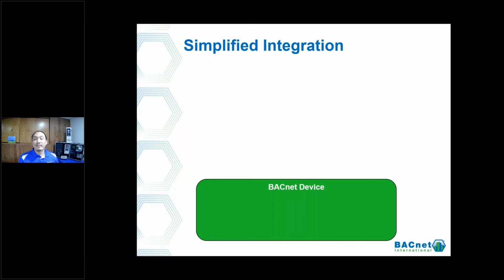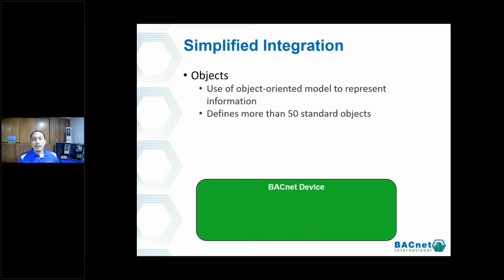Now that I know what my device is going to be, I need to define what's inside it. BACnet uses more of an object-oriented approach, so the data is put together and assembled in a structured way. There are more than 50 standard objects — BACnet, or ASHRAE, has defined a whole bunch of standard objects that specify how the data looks and how it's formatted.